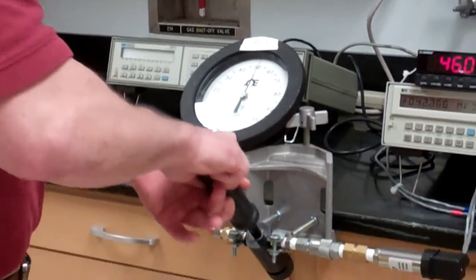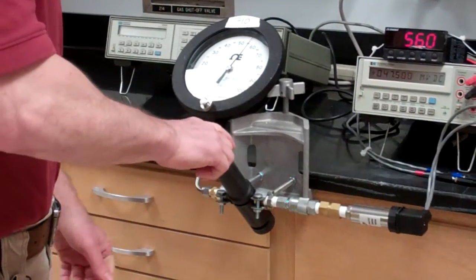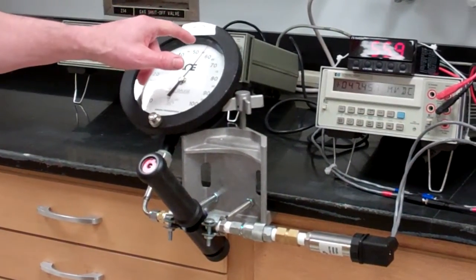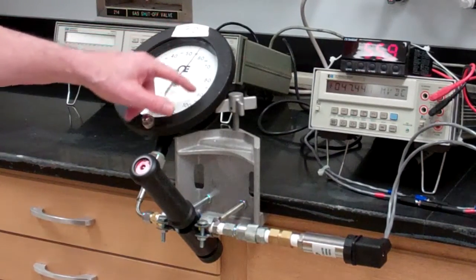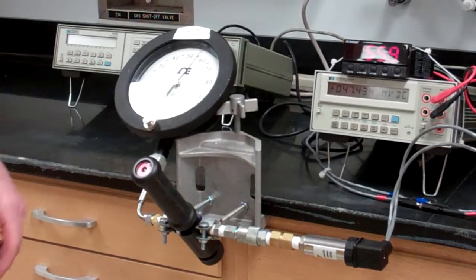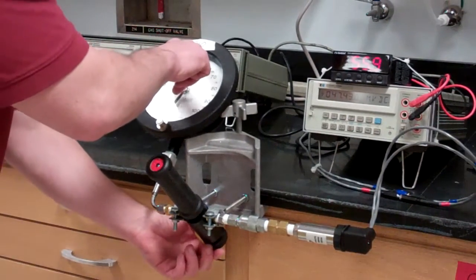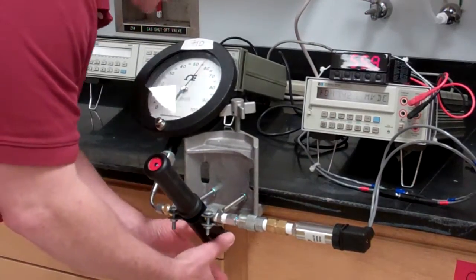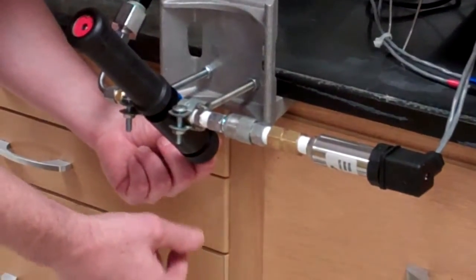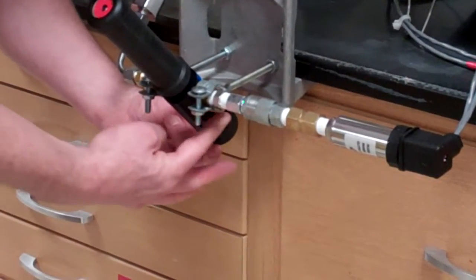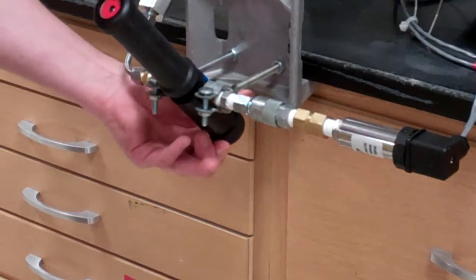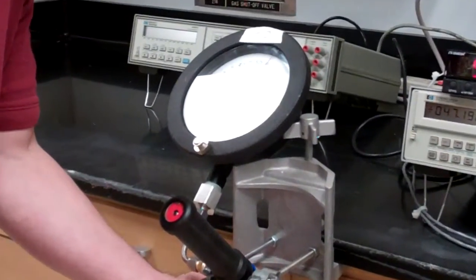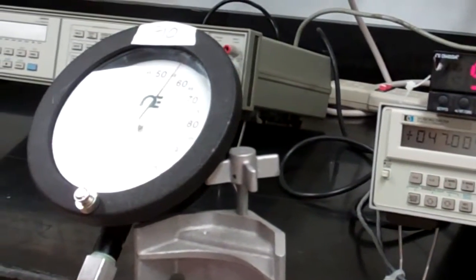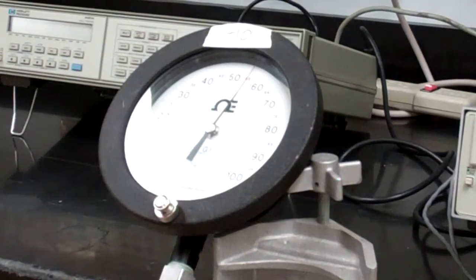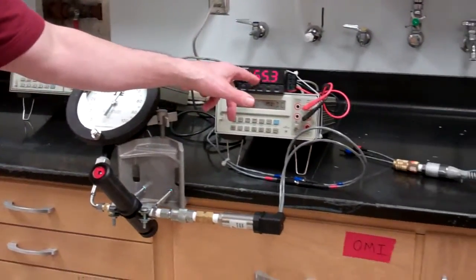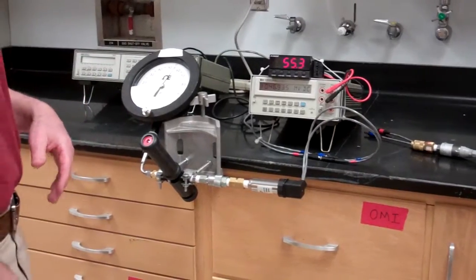And let's say that we're going to go to 50 psi or 55 psi. You can take this up to 100, but of course don't go over 100 in terms of safety. So let's say I wanted 55, but I'm a little bit above 55. There's another knob down here. So there's a little knob that's a bleed valve, and there's a big knob that actually changes the volume inside here. And by increasing the volume a little bit, it's going to decrease the pressure. And so I can dial it in to get right at 55. So very precise. Now, it's okay that the display meter doesn't read exactly what the pressure gauge does, but that's one of the things you're going to investigate.